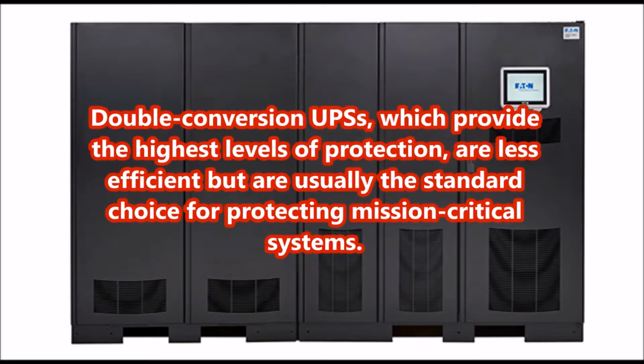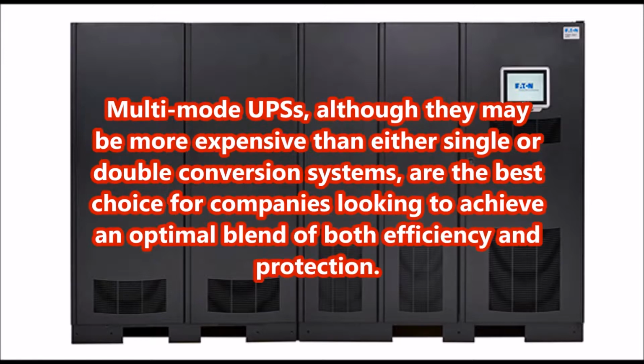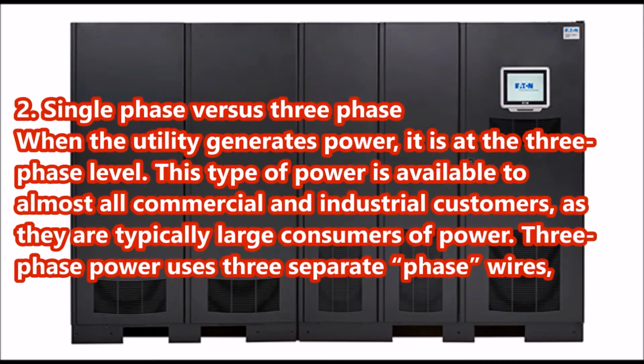Double conversion UPSs, which provide the highest levels of protection, are less efficient but are usually the standard choice for protecting mission-critical systems. Multi-mode UPSs, although they may be more expensive than either single or double conversion systems, are the best choice for companies looking to achieve an optimal blend of both efficiency and protection.